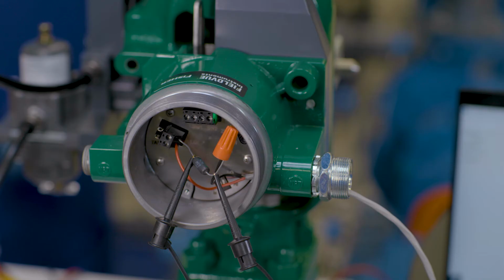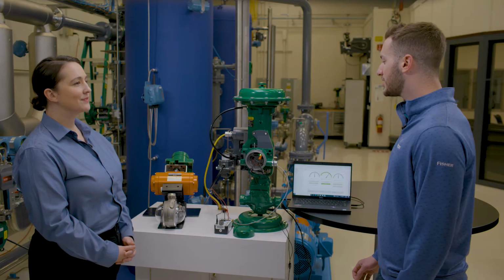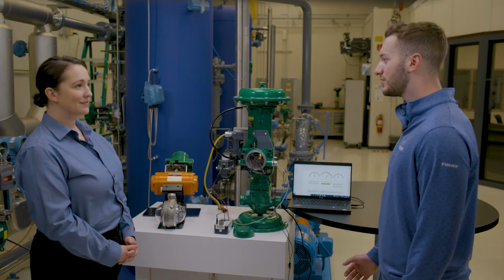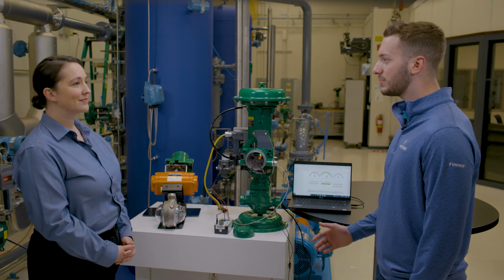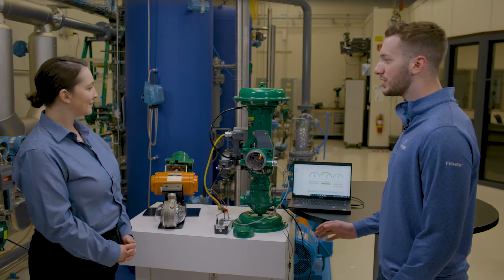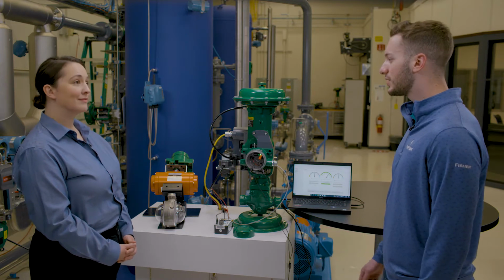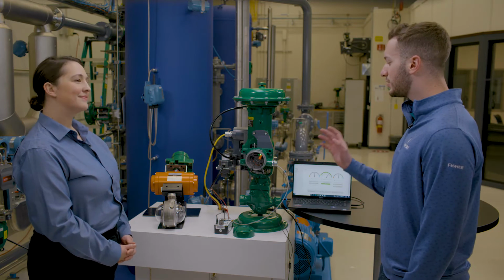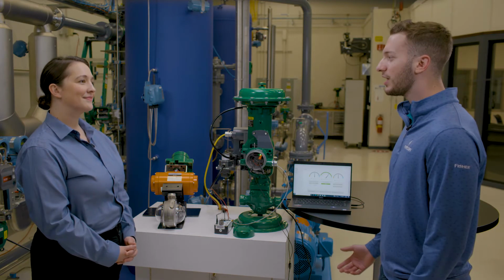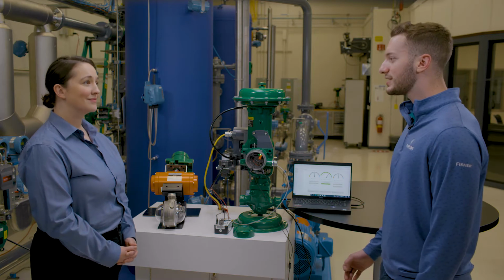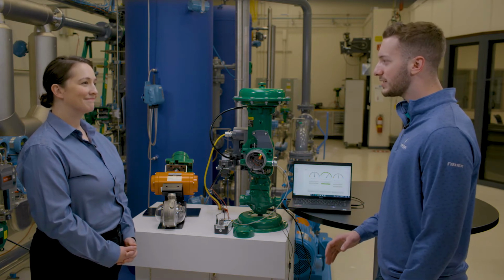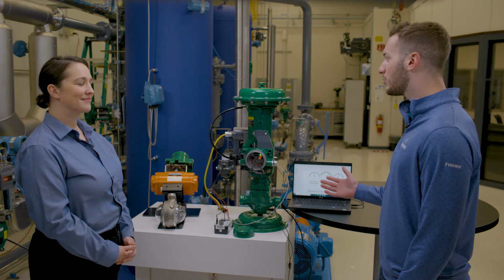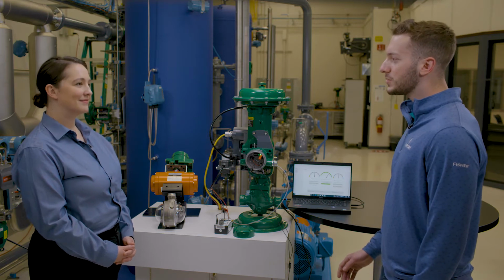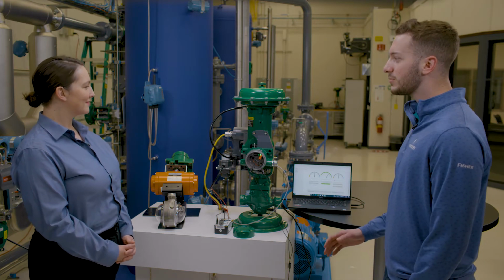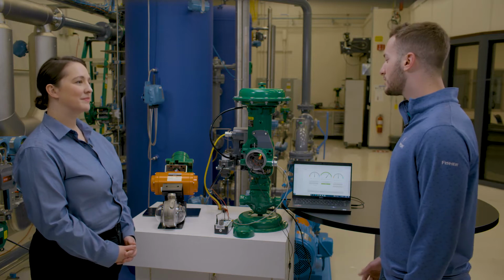And what makes the 4400 different? Well, there's several differences with the 4400. First is the linkageless, non-contact position feedback that increases reliability by eliminating any vibration concerns that you would see with mechanical linkages. Second is the ease of use, because you can calibrate the device in a fraction of the time. And then third is diagnostics, which enables maintenance to see details about the valve before they go on site. It also enables proactive practices in the same way our digital valve controllers do, using similar diagnostics.